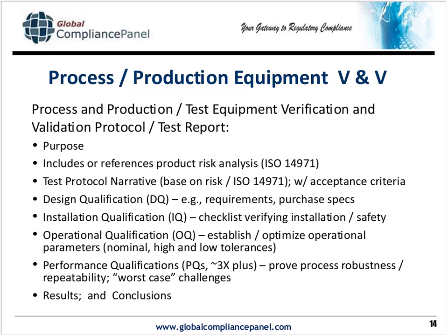So it's up to you to determine what the issues are based on risk, and then provide the documentation to show that those have been fully addressed. But anyway, the OQ proves that everything has been optimized. And so you've established your nominal operating tolerances and the range, the high and low range. And then you run your process over a lengthy period of time to show perhaps that at nominal, at high, at low, at some combination, that everything works.